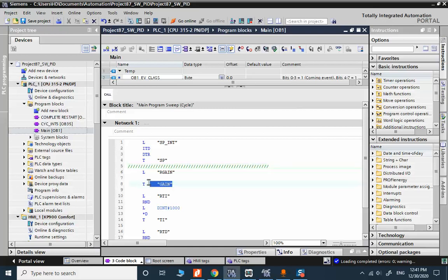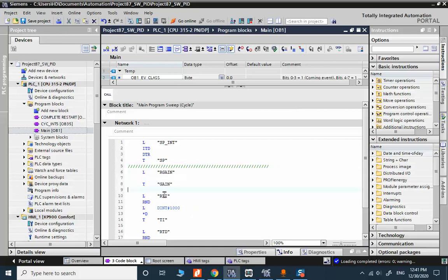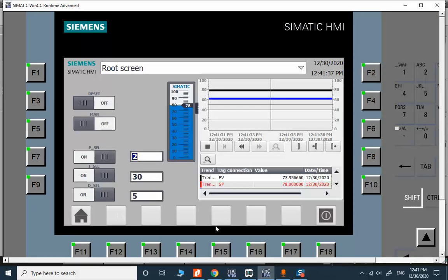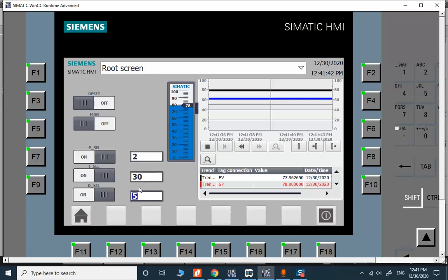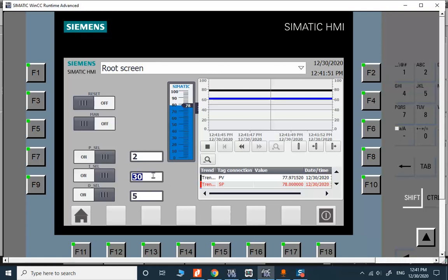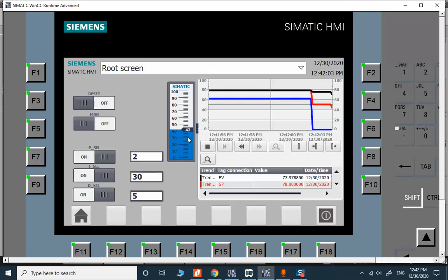Let me open the OB. The gain is in floating point format, it's only possible to just make a copy. But for integration time, the integration time in HMI is in the real format and the derivative time is also in the real format and I need to change them to the time format because the PID block just accepts the time format.